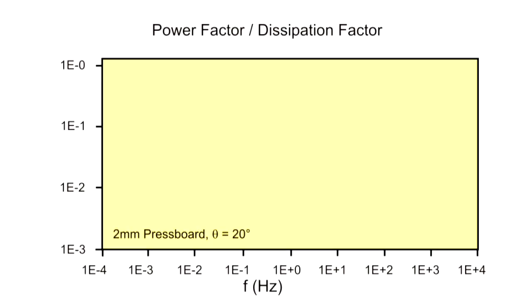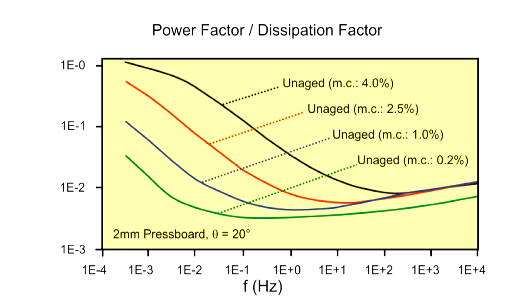The dissipation factor or the power factor depends strongly on the water content of the cellulose in oil. This curve is the result of relatively dry cellulose with water content of 0.2%. This curve has 4% water content.